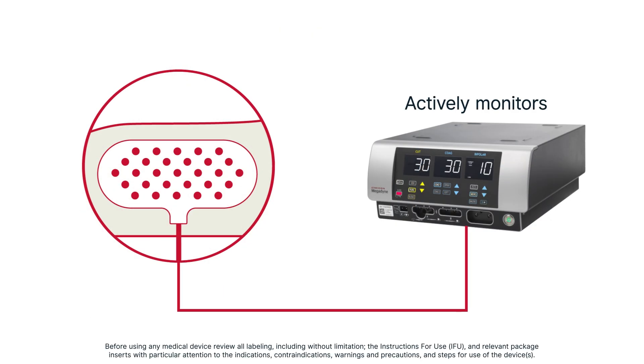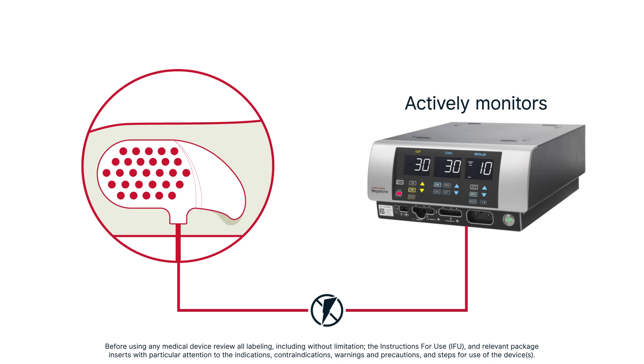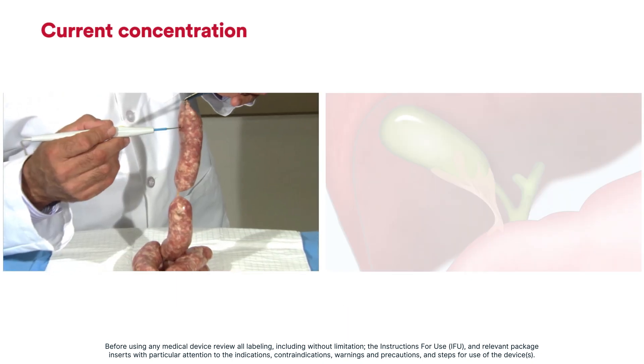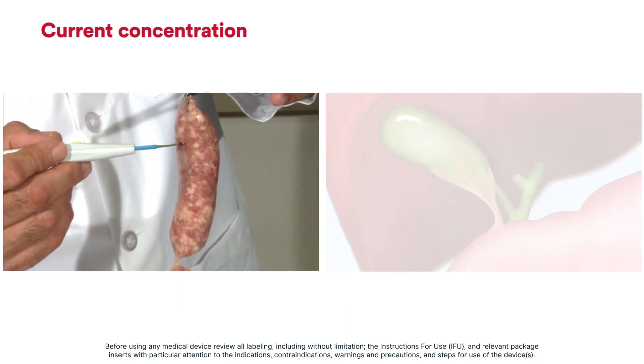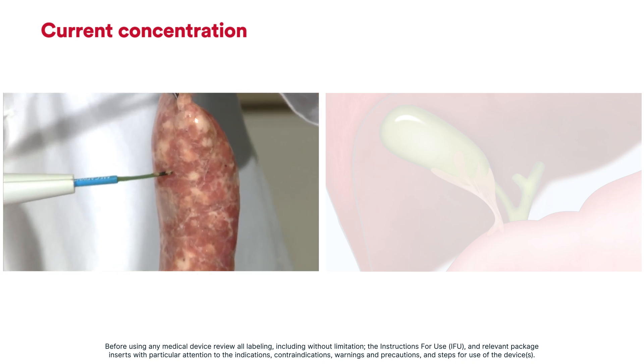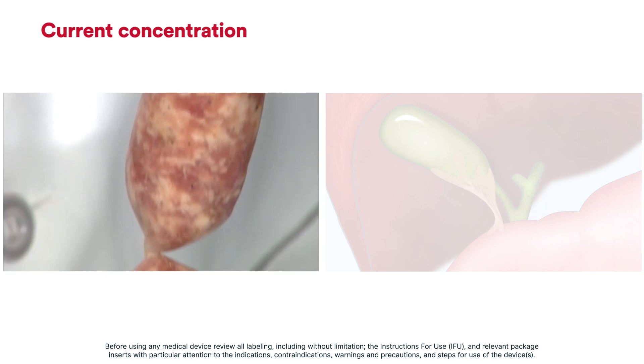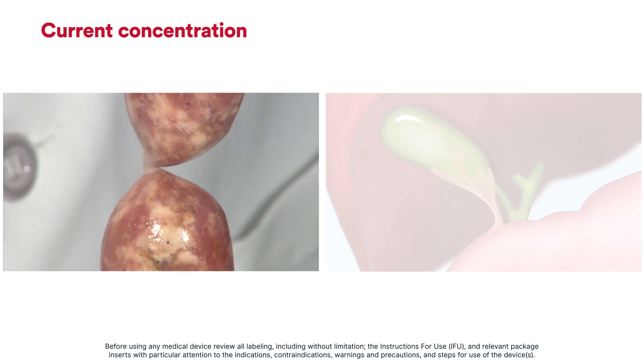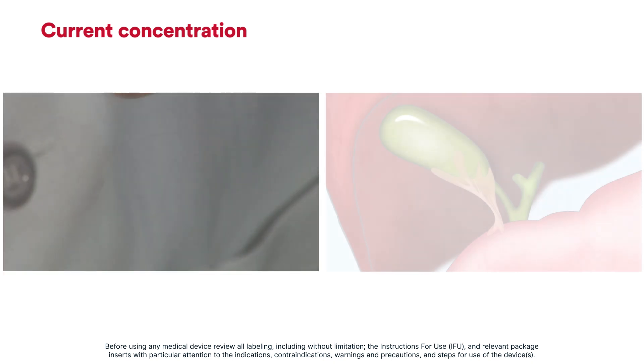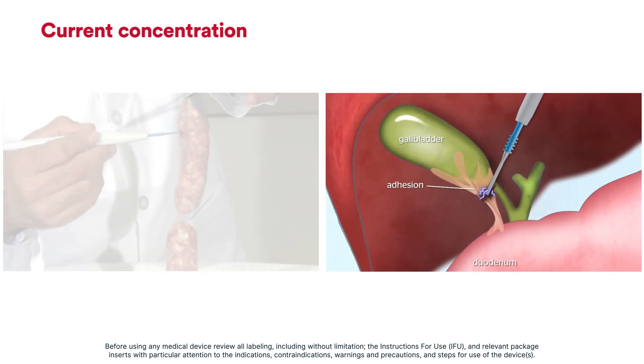Most modern electrosurgery systems monitor resistance at the return electrode to detect adequate patient contact. These generators will stop the flow of electricity as a safety measure to prevent injury from concentrated current flow at the single-use sticky pad. This video demonstrates the effects of current concentration. Though the energy is being applied to the top sausage, current passes through all the sausages to the return electrode on the benchtop. As current passes between the links, the narrow cross section concentrates the current, causing unintended damage. In a practical example of taking down an adhesion between the gallbladder and duodenum, applying energy can cause unintended damage on the other end of the adhesion.